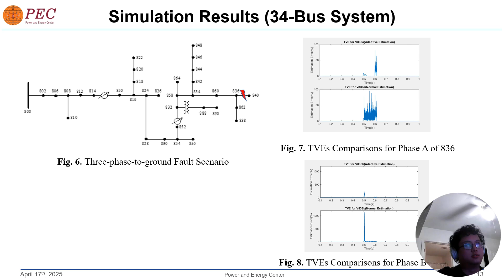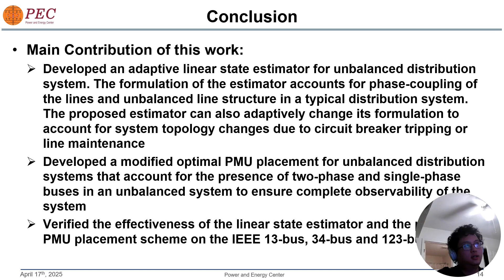This brings us to the conclusion. The main contributions of this work are threefold. Firstly, we developed an adaptive linear state estimator for unbalanced distribution systems. The estimator can adaptively change its formulation to account for system topology changes. Secondly, we developed a modified optimal PMU placement scheme that can guarantee complete observability for an unbalanced distribution system. Thirdly, we verified the effectiveness of the linear state estimator and the proposed PMU placement scheme on the IEEE 13, 34, and 123 bus systems. That concludes my presentation.